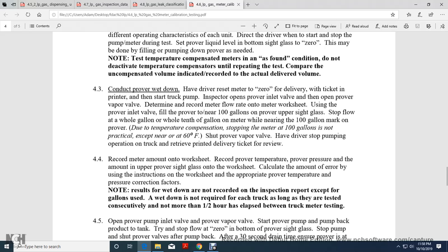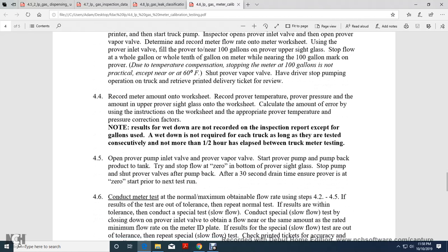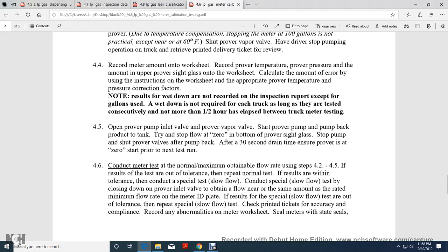Due to the temperature compensation, stopping the meter at 100 gallons is not practical except near 60 degrees Fahrenheit. Shut the prover vapor valve. Have the driver stop the pumping operation and retrieve the printed delivery ticket for review. Record the meter amount on the worksheet. Record the prover temperature, prover pressure, and the amount in the upper prover sight glass on the worksheet. Calculate the amount of error using the instruction worksheet and the appropriate prover temperature and pressure correction factors.